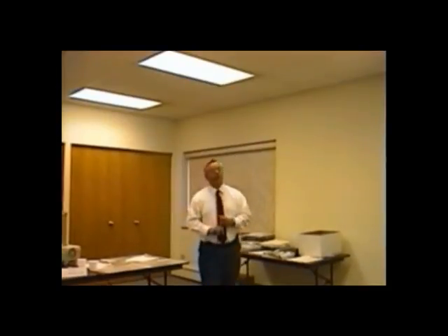Today we could have 25 over ambient. We could have 20 over ambient. We could have 15 over ambient. And I can even show you a chart where it shows 11 over ambient. So if we do charge those to 30 over ambient, again, we are overcharged, okay? All right, so let's go over here.